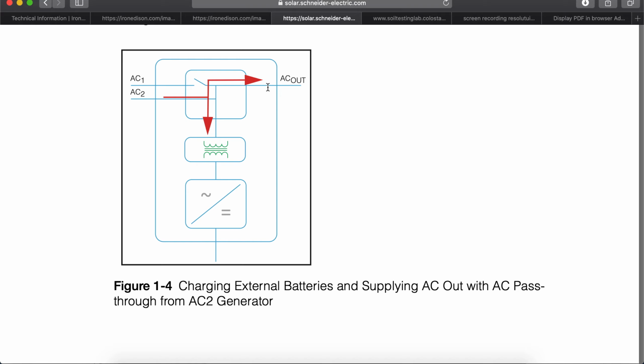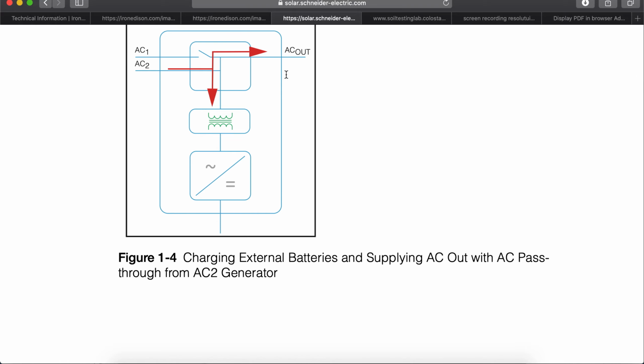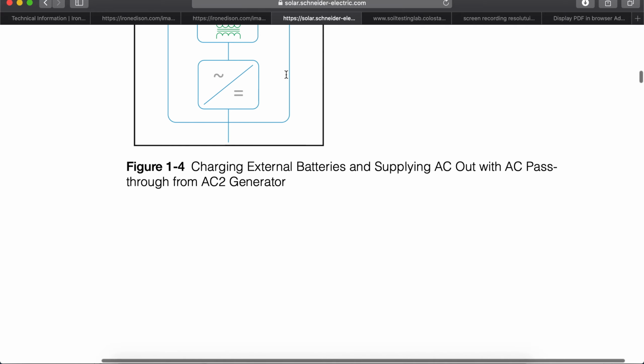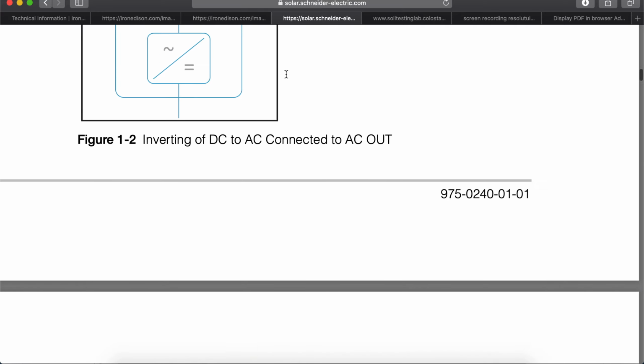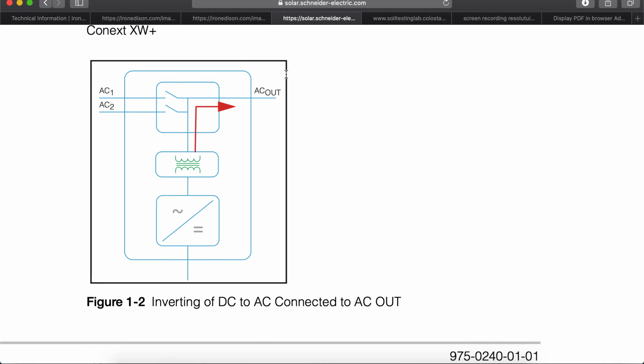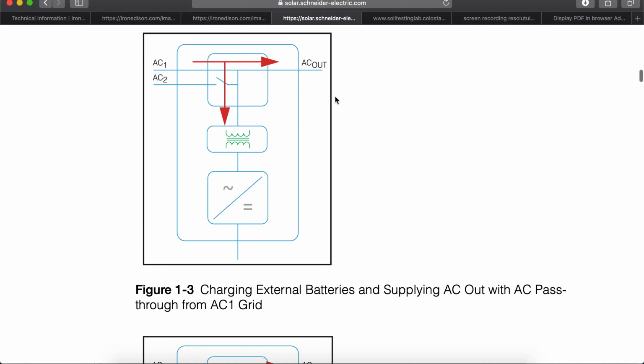So at the same time as battery charging, the inverter is going to take some of that generator AC power and simply pass it through to keep everything powered up while the battery's charging. Once the generator turns off, we're going to go back to this operation. Inverting of DC to AC connected to AC output. So again, once that generator stops, we disconnect the grid. See, we're disconnected, no AC input sources. The inverter is powering the load simply based on inverting battery, solar, any other DC input source connected to the bottom of the inverter, giving you grid-like AC output on a protected circuit breaker box.